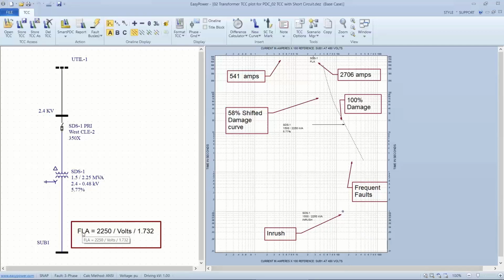And this is based upon the full load current, which is equal to the MVA rating or KVA rating divided by the voltage and divided by the square root of 3. So that'll give us the full load current, which is up here at the top. And as we isolate on that or put the cursor on that, you'll notice down here at the bottom, it tells me what the coordinates for that particular cursor location is. And that will be something very near to the 2706 full load current amps. Again, this is in a 480 volt environment.